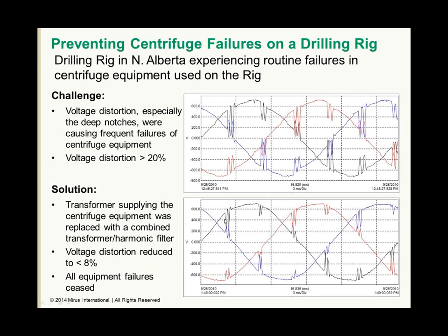And as they commutate, if there's a phase-back angle, they'll introduce voltage notch, and that notch can be quite severe when there's no treatment. We can see the notch is substantially lower. It's about half the depth as it was without the treatment, and that was enough to eliminate all of the failures. Again, for those interested, we have an IEEE peer-reviewed technical paper describing this application, which can be found on our website.